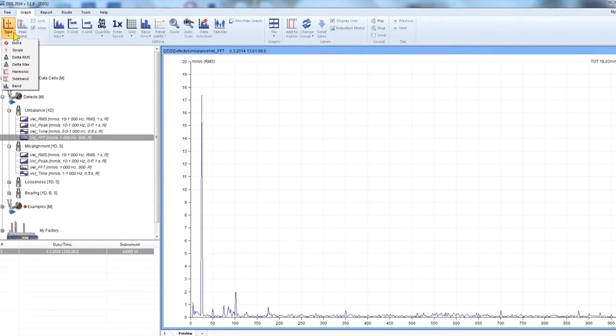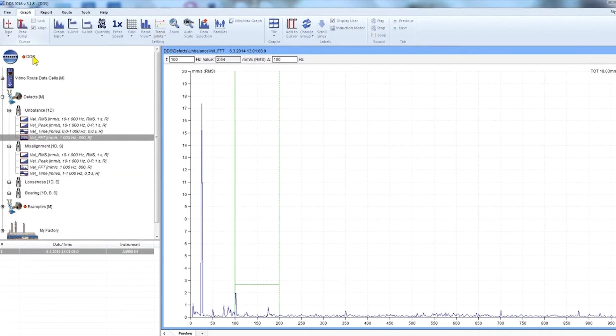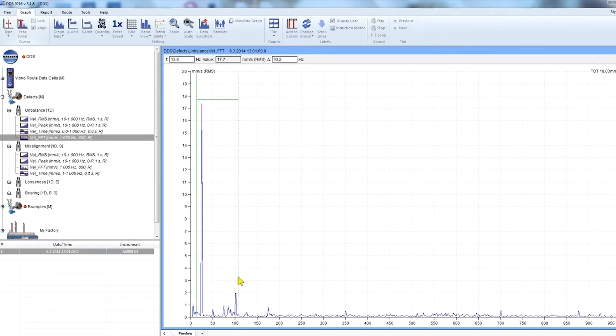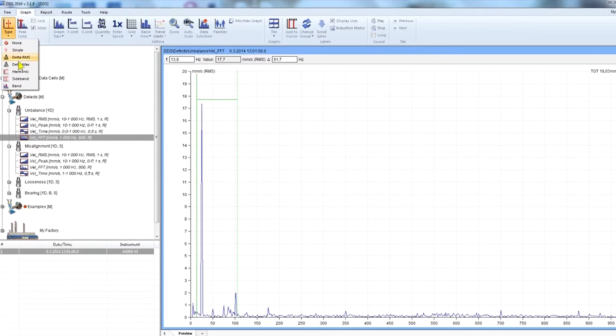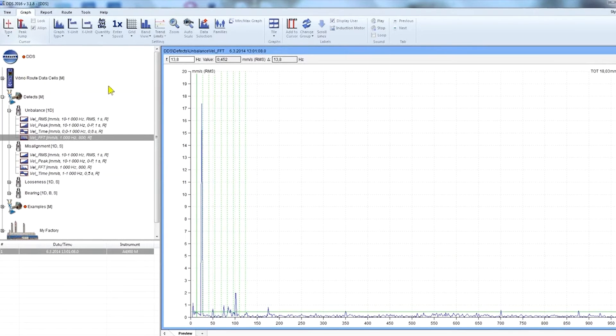There are more types of cursors for dynamic readings. Select the type button and you can see the types: simple, delta RMS, and delta max. With delta RMS I can extend a range and see the RMS value of the energy of the selected range. Another type is the harmonic cursor, where you can look for harmonic components of the running speed.